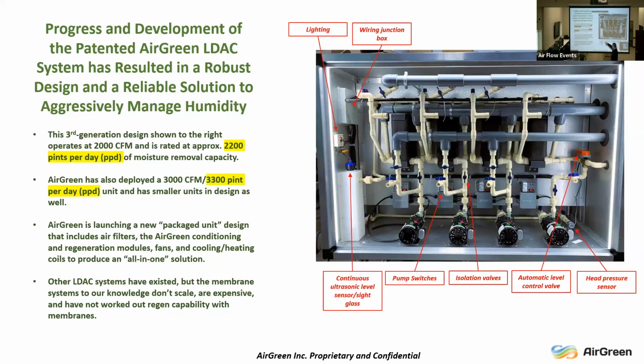Like I mentioned before, this is a 2000 CFM unit. Earlier designs were velocity limited. You do not want to create carryover. You don't want to carry your salt solution downstream into ductwork and your customers' stuff. So we were managing our velocities pretty low. We've since done some things differently that allow us to move those velocities even higher. So this 2000 CFM unit is likely to become a 2500, and its moisture removing capacity will also go up. With the added performance that we've achieved, the units for the same work can become smaller and less expensive.